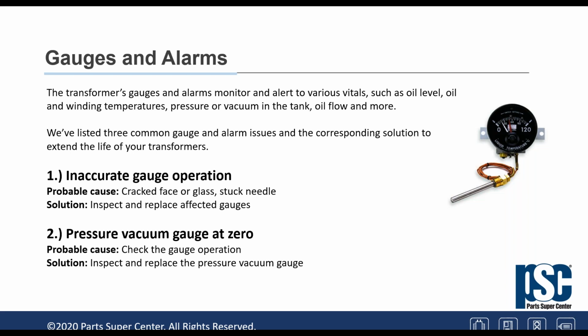As a matter of fact, item 2, pressure vacuum gauge at 0. That's another thing that can never happen, because again, if the transformer tank is sealed, it will very seldom be zero; it will be either positive in summertime or negative in wintertime. If there is a zero, rest assured that either the needle is stuck or the gauge is defective.